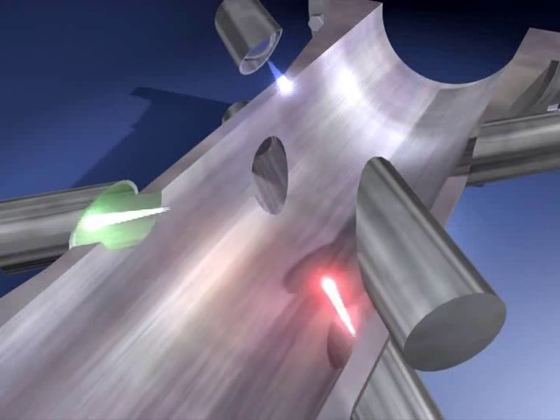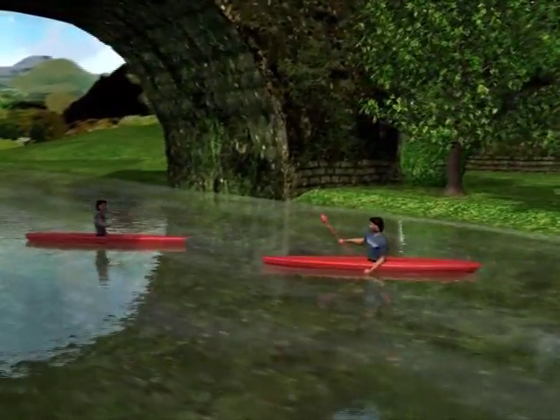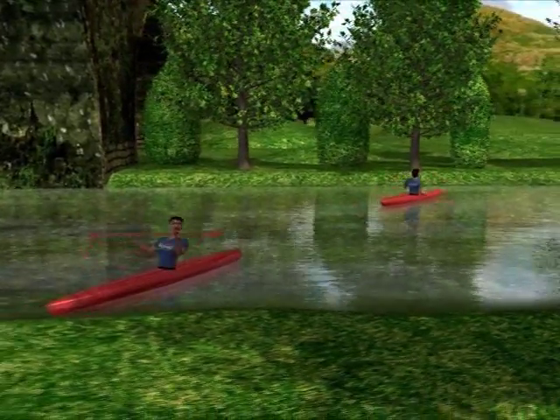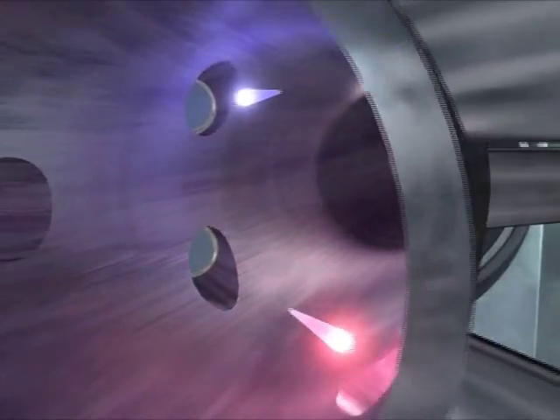But how does this work? Ultrasonic measurement is based on a simple physical fact. Imagine two canoes diagonally crossing a flowing river. The canoe moving with the flow needs much less time to cross. Consequently, the difference between the two times is directly proportional to the flow rate. This simple, yet exceptionally accurate principle forms the basis of Krohne's Ultrasonic 3.